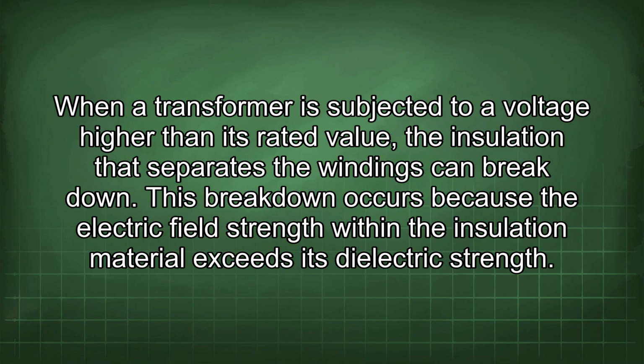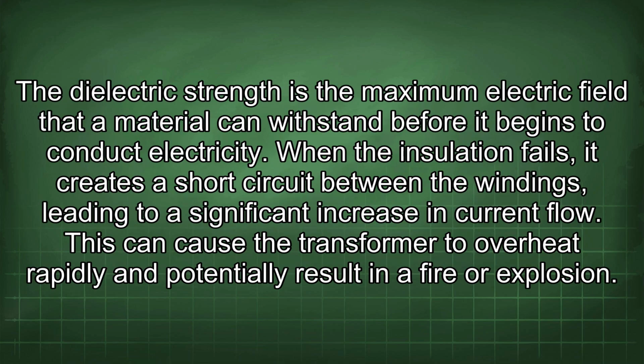When a transformer is subjected to a voltage higher than its rated value, the insulation that separates the windings can break down. This breakdown occurs because the electric field strength within the insulation material exceeds its dielectric strength. The dielectric strength is the maximum electric field that a material can withstand before it begins to conduct electricity. When the insulation fails, it creates a short circuit between the windings, leading to a significant increase in current flow. This can cause the transformer to overheat rapidly and potentially result in a fire or explosion.